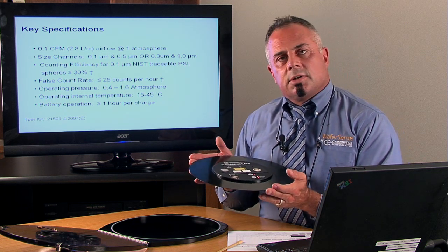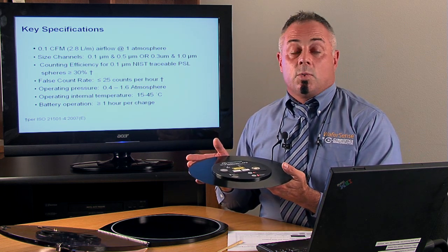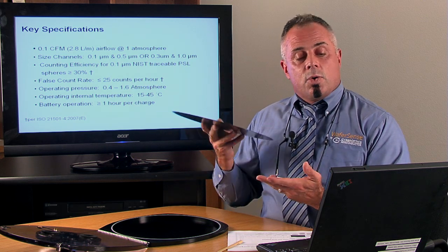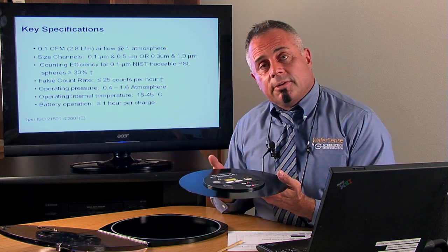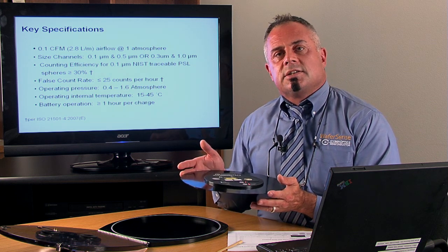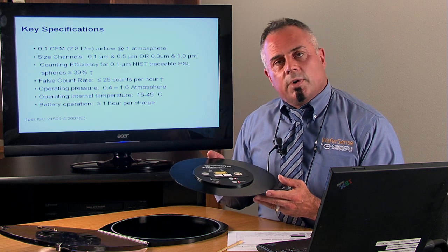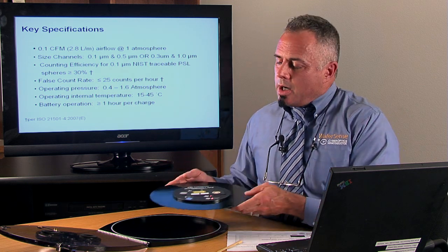Operating pressure is 0.4 atmosphere to 1.6 atmosphere. And also the operating temperature it's calibrated for, for accurate particle counting, is 15C to 45C. APS will run approximately one to one and a half hours on a single charge.